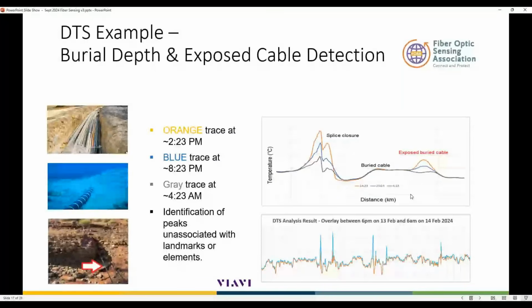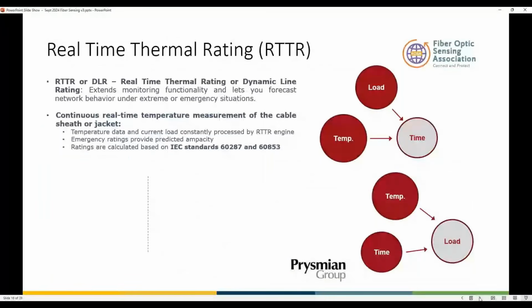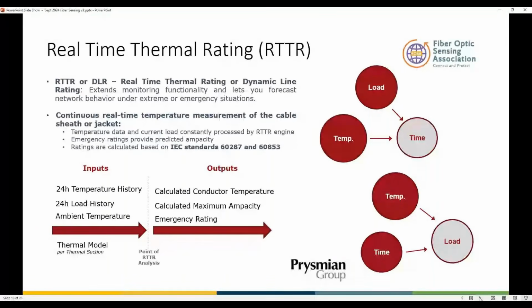So just a practical example there. I'll talk briefly about real-time thermal rating, or dynamic line rating. It's a computational engine or methodology that's standards-based, per IEC standards 60287 and 60853, for operating transmission lines at maximum efficiency, and when applied over time it can also lengthen the lifespan of the asset.